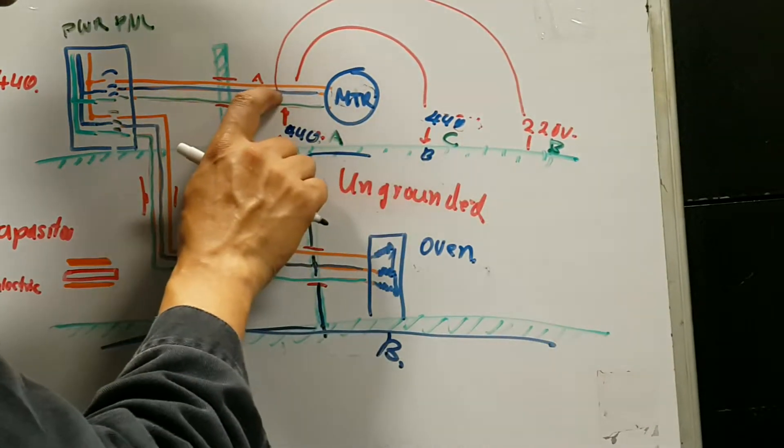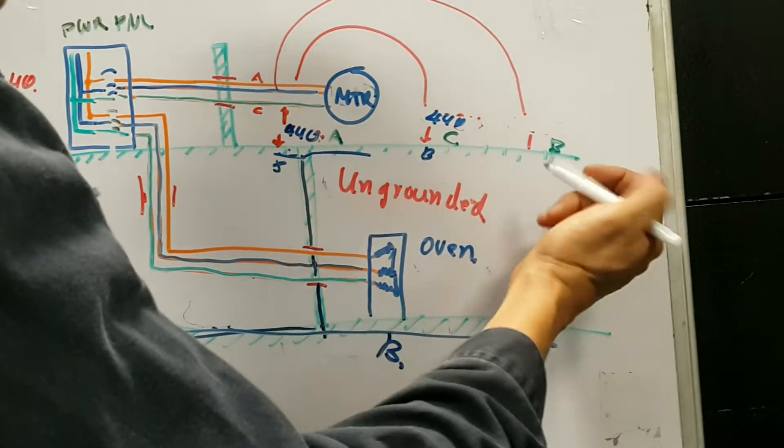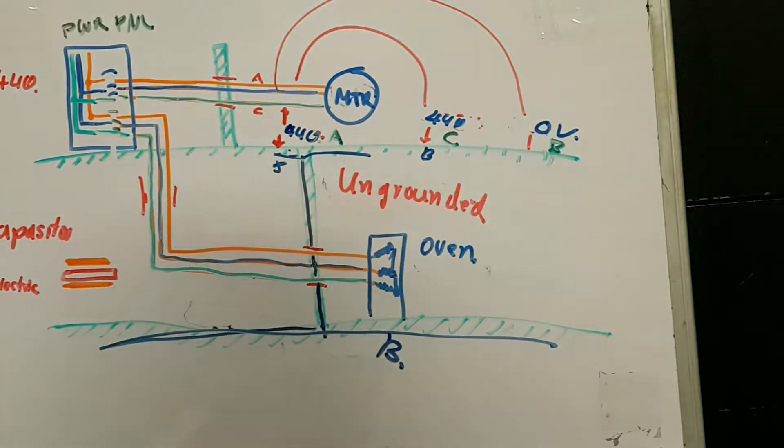But now let's look at this one. This phase is B potential, and the ship is B potential. So the difference of potential will be 0 volts. If you ever see one phase to ground 0 volts, that means it's grounded.